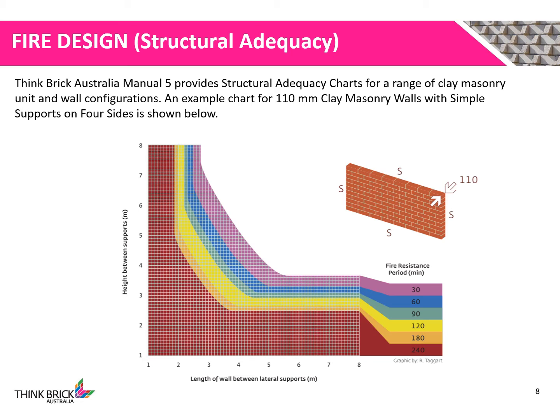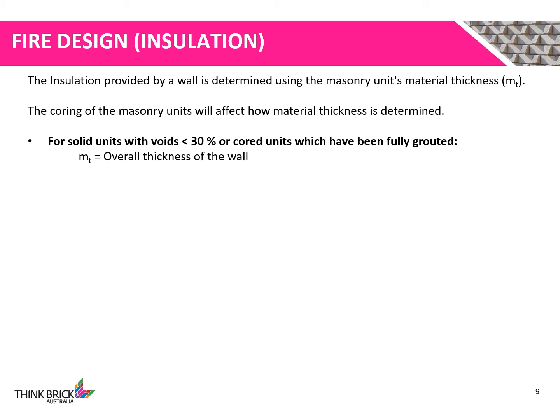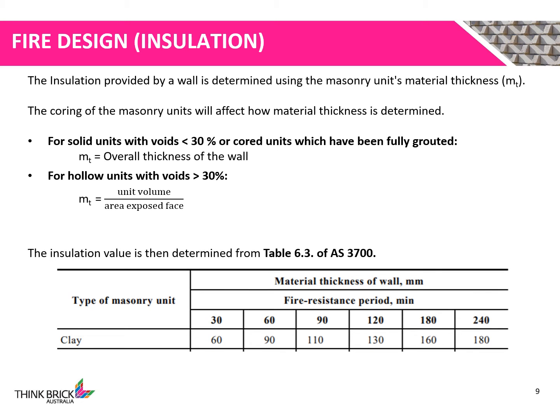An example chart for a 110mm thick clay masonry wall simply supported on all four sides is shown. The insulation provided by a wall is determined by the masonry unit's material thickness. Coring of masonry units will affect how the material thickness is determined. For solid units with voids smaller than 30%, or cored units which have been fully grouted, the material thickness is equal to the overall thickness of the wall. For hollow units with voids greater than 30%, the material thickness is equal to the unit volume divided by the area of the exposed face. Once material thickness is determined, Table 6.3 of AS 3700 can be used to identify the insulation fire resistance period.